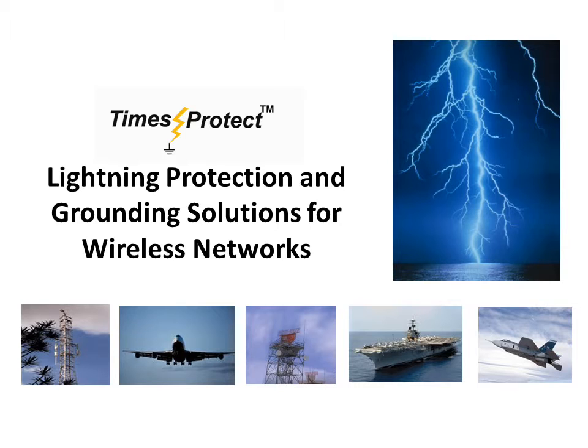The basic function of an RF lightning surge protection device is to limit voltage and energy to the protected equipment by conducting surge current to the shield or ground during lightning events. One important factor in the selection process is whether the application requires RF only or if it requires DC voltage and current on a center conductor to power tower top electronics.